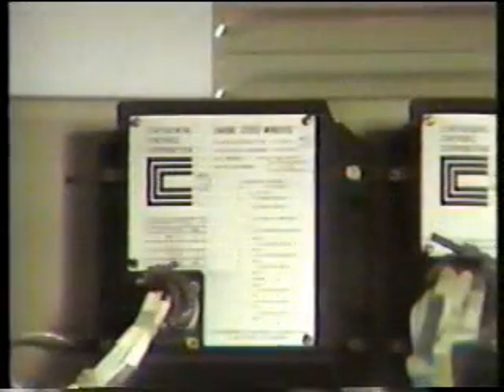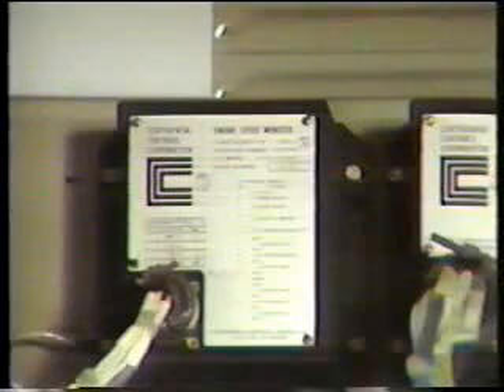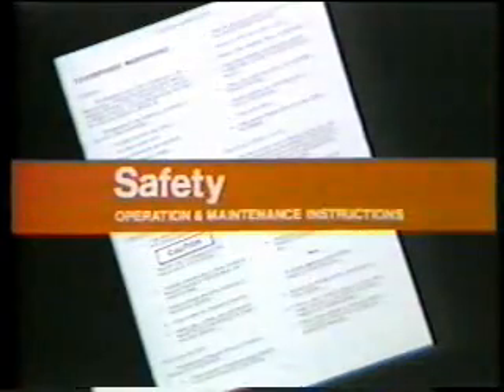Calibration of the speed control system is performed as part of the intermediate maintenance inspection to verify the proper operation and set points of the engine speed control unit Z283. Be sure to check your operation and maintenance instructions for warning and safety precautions that pertain to speed system calibration.